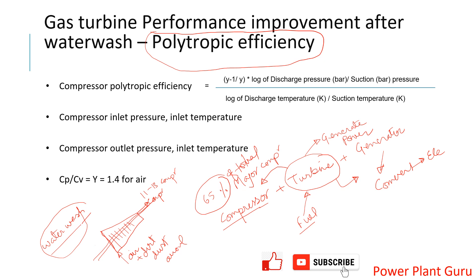To calculate polytropic efficiency, you use this formula: gamma minus one divided by gamma, multiplied by the logarithm of discharge pressure divided by suction pressure, all divided by the logarithm of discharge temperature divided by suction temperature. Discharge pressure is the compressor outlet pressure; suction pressure is the ambient or atmospheric pressure. Discharge temperature is the compressor outlet temperature (CTD), and suction temperature is the ambient temperature. After water wash, you will see a significant improvement in the discharge pressure.